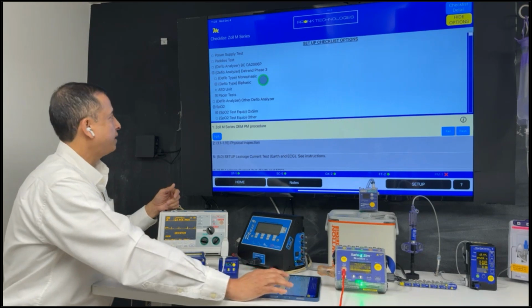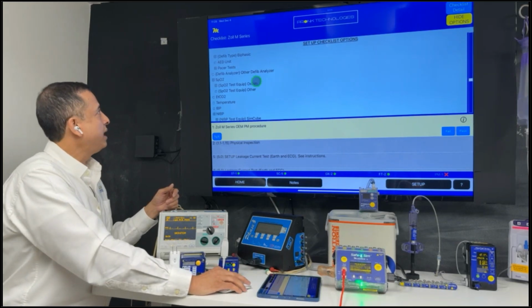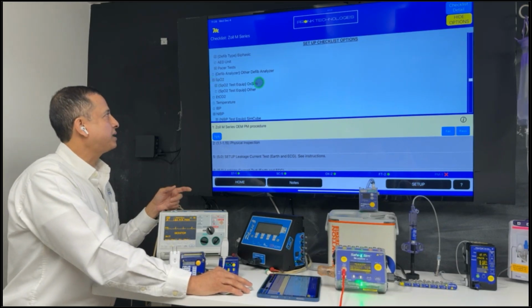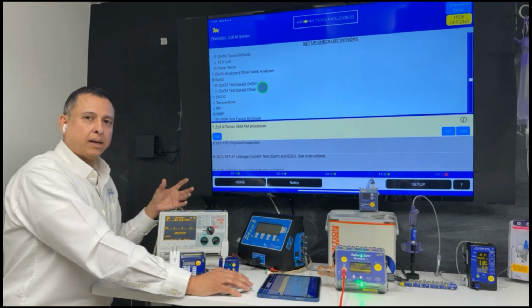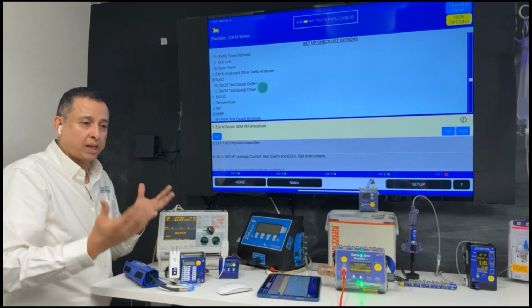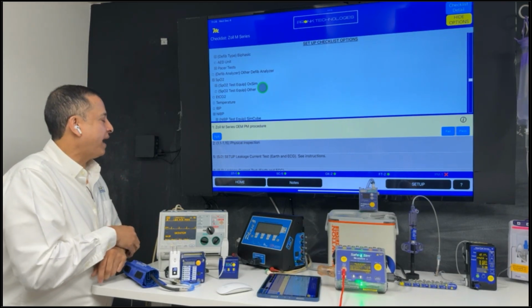So you can see here, depending on what kind of Zoll M I'm testing and what options it has, I could select these other tests. So I'm going to go ahead and just enable Pacer test. I'm going to enable an SpO2 test. And you can see I could pick OxSim. Or if I don't have an automated Mobilize compatible device, I can select other equipment. Maybe I don't have a Mobilize compatible device at the moment, but I still want to run the procedure. So you could select other and it will allow you to manually enter that result.